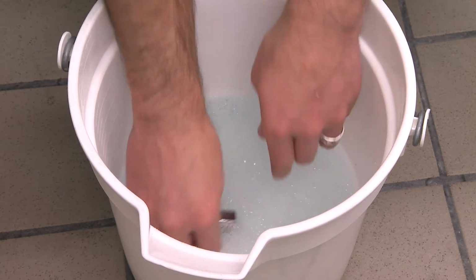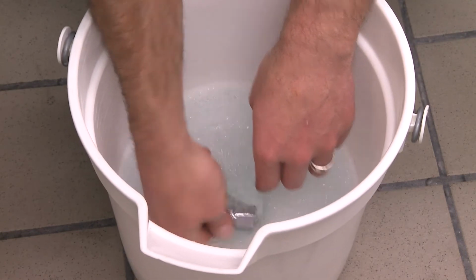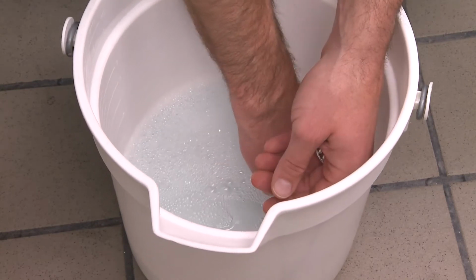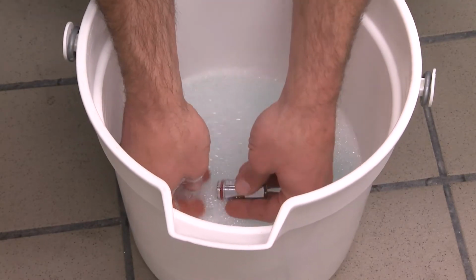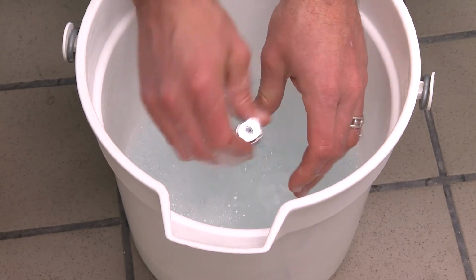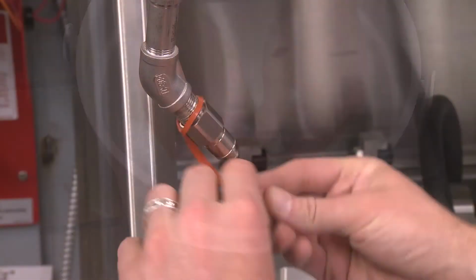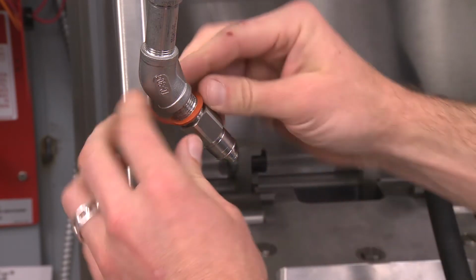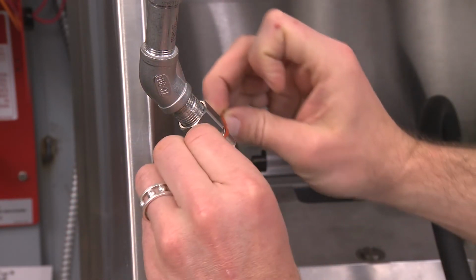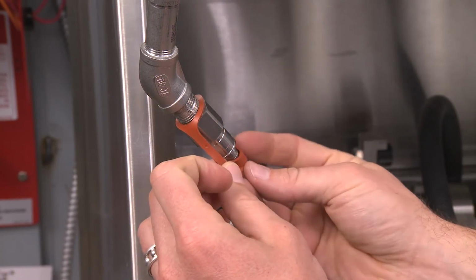Again, if nozzles show signs of cooking grease in the orifice of the nozzle, or if there is agent residue in the nozzle or the inlet to the agent distribution piping, some or all of the piping may be dismantled to verify the piping is not obstructed. Finally, all rubber nozzle blow-off caps and O-rings used with the larger metal blow-off caps on the current nozzle design must be replaced.